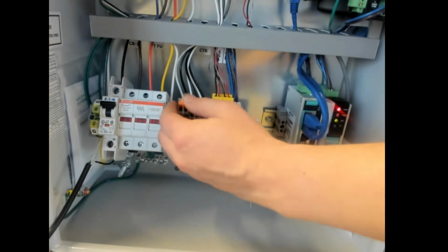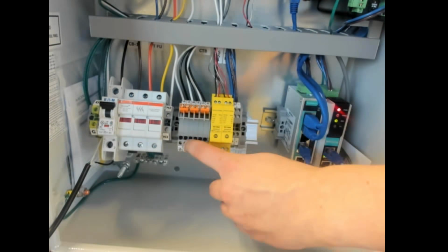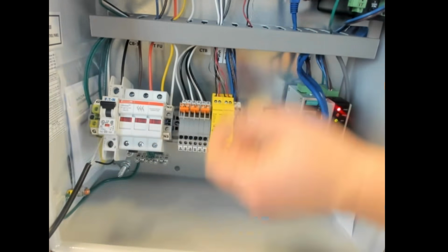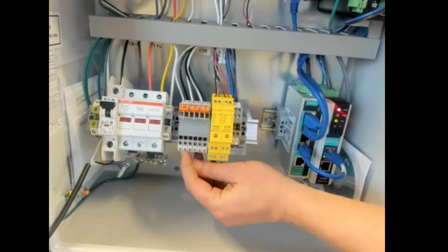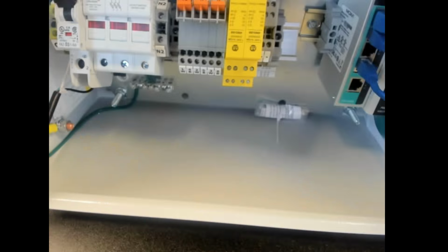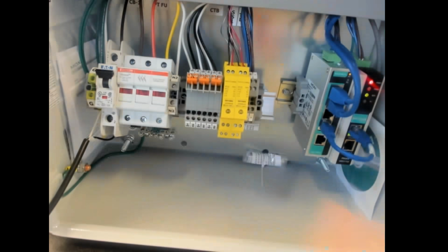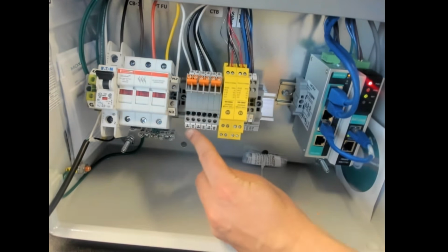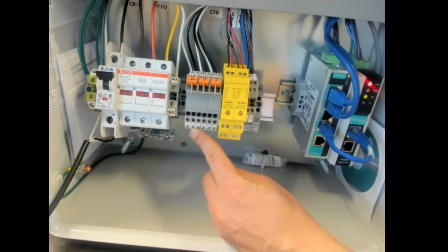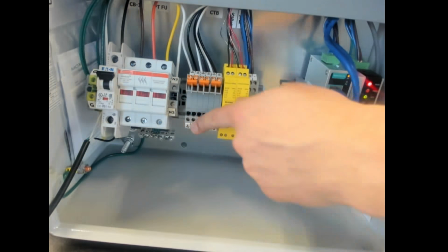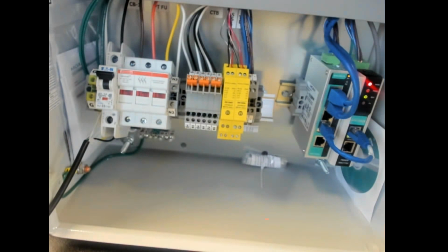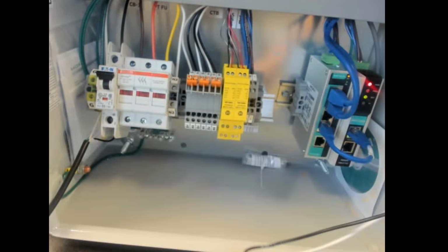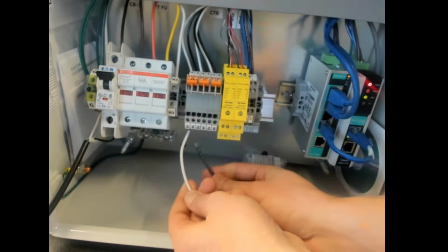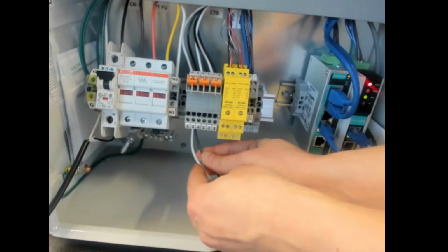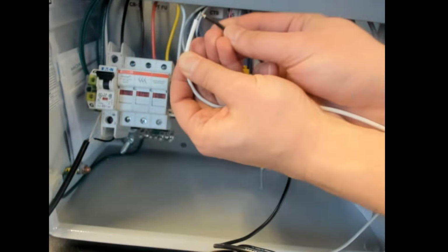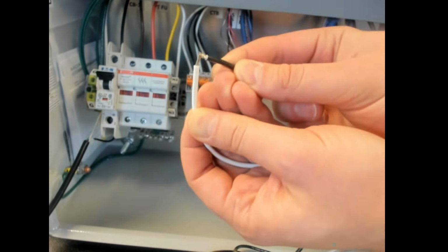So if I insert this back into the actual terminal block and I have these CT lines here, let's say it's phase A, white and black, and the labels are pretty good on this one. So you'll see white and black, it's 1 row instead of the stack. So phase A would go here, white 1, and then black 4. And basically what that means is any kind of currents that might be flowing through the CT and eventually going through the CT leads, that is as if they were physically connected here. So it's a closed loop system.